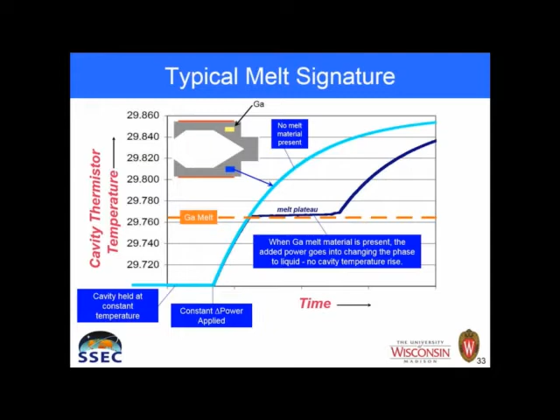Okay, so how do we do this temperature business? This is illustrated on a curve, which is temperature versus time. And this is a heated cavity with a thermistor in it. So this trace here is the temperature that would be reported by that thermistor. And we take this cavity and go into a constant temperature right under the melt point of gallium. And when we process, we go into a constant power mode. We just give it a little shot of power, which makes it exponentially rise to a new equilibrium temperature. But that's what would happen. But if you put even a little bit of gallium in this system, something different happens. When you approach the melt temperature of the gallium, that power goes into changing the phase of that gallium, and it puts a kink in this exponential curve. Then it climbs out and reaches the equilibrium temperature. And so this is the signal that we're looking for that tells us we're melting gallium.